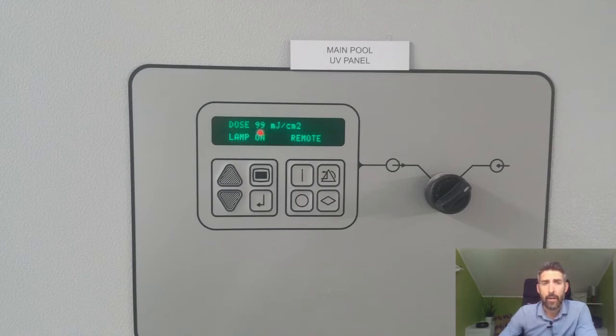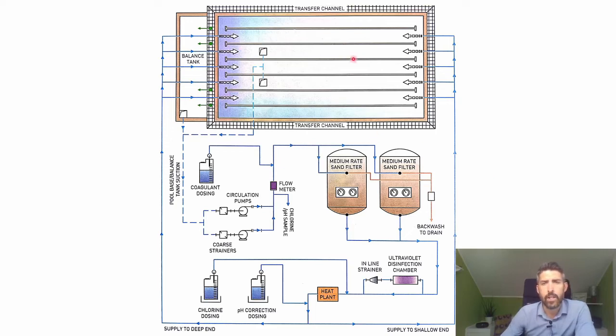Ultraviolet disinfection is referred to as a non-residual disinfectant, which is unlike chlorine, which is a residual disinfectant. With chlorine, when it's injected on the schematic here, the water goes back and circulates to the pool. You've got chlorine dissolved in this water, so there's always a residual of chlorine there. As the water exits the pool and circulates around the system, there's still chlorine in the water all the way along here.